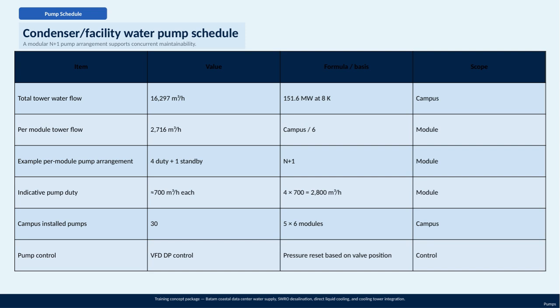Altogether, across the campus, there are 30 pumps installed, aligned with the 6 modules. For control, we use variable frequency drives with differential pressure control. This means pump speed adjusts dynamically based on valve position, optimizing pressure and energy usage throughout the system. This combination of modularity, redundancy, and smart control is key to maintaining efficient, reliable cooling for the data center.